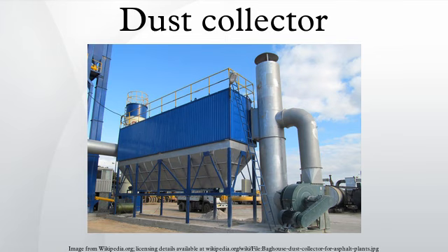Fabric filters. Commonly known as baghouses, fabric collectors use filtration to separate dust particulates from dusty gases. They are one of the most efficient and cost-effective types of dust collectors available and can achieve a collection efficiency of more than 99% for very fine particulates. Dust-laden gases enter the baghouse and pass through fabric bags that act as filters. The bags can be of woven or felted cotton, synthetic, or glass fiber material in either a tube or envelope shape.